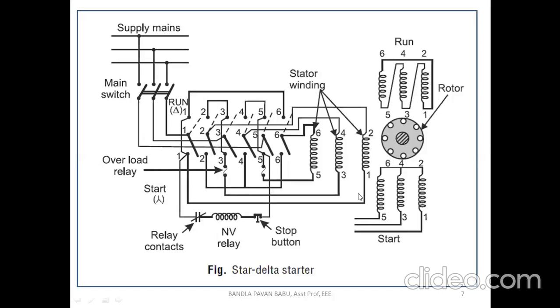So here, in the stator winding, all the phases will have terminals in the terminal box, as we have seen in the construction details of the induction motor. There you can see all the phases, and the starting and ending ends will be tapped there. Accordingly, with the help of the changeover switch, we are going to tap the connections. If it is pulled downward, towards our side, then it gives the star connection. If it is in the opposite direction, then it is delta connected.